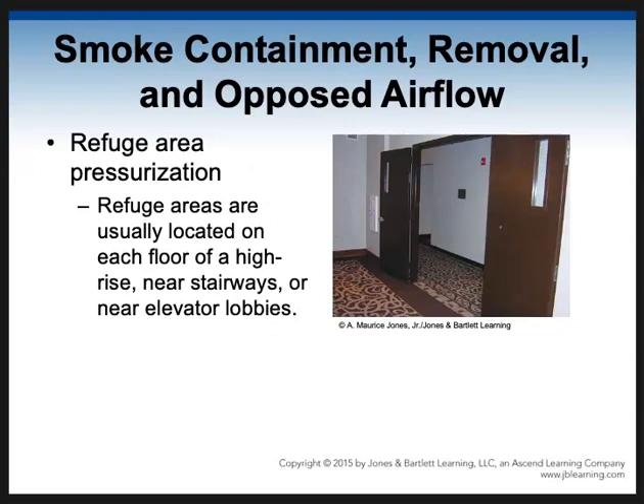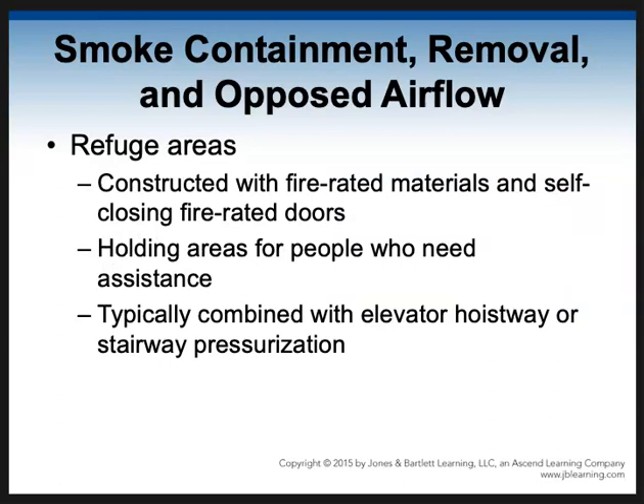Now, another thing that they do with pressurization is refuge areas. These are common in high-rise buildings and buildings with handicapped or ill people, like hospitals and large convalescent homes. They'll create refuge areas, and a lot of times they're right near where the elevator is, and they have doors that automatically close, very thick fire-rated walls. The ductwork will automatically close so smoke can't come in or go out, and they'll pressurize that room with fresh air, hopefully giving the firefighters time to suppress the fire and evacuate these people in a safe manner. So these are oftentimes near stairways or near elevator lobbies. The refuge areas are going to have that fire-rated material, and they're holding areas for people who need assistance.